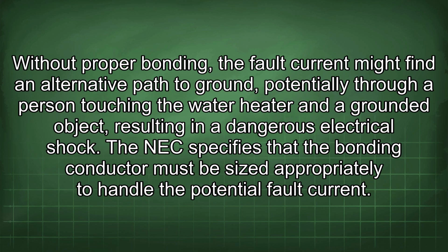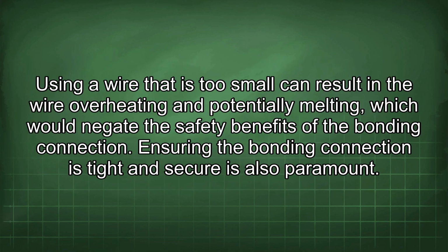Without proper bonding, the fault current might find an alternative path to ground, potentially through a person touching the water heater and a grounded object, resulting in a dangerous electrical shock. The NEC specifies that the bonding conductor must be sized appropriately to handle the potential fault current. Using a wire that is too small can result in the wire overheating and potentially melting, which would negate the safety benefits of the bonding connection.